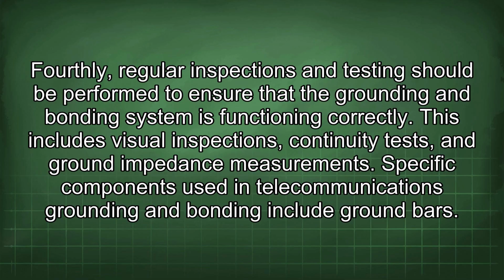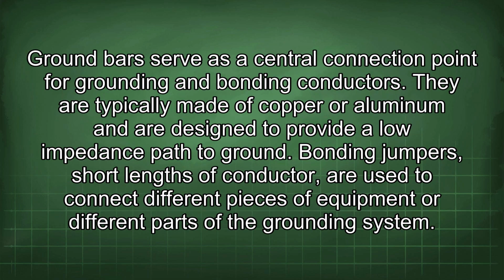Specific components used in telecommunications grounding and bonding include ground bars. Ground bars serve as a central connection point for grounding and bonding conductors. They are typically made of copper or aluminum and are designed to provide a low impedance path to ground.